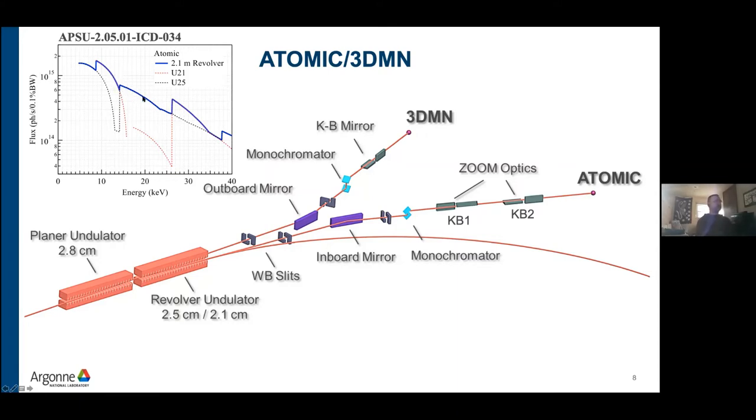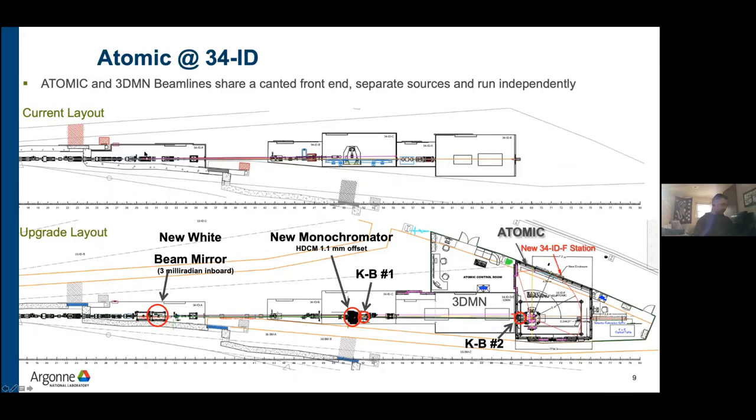The undulators we chose were a 2.5 cm period and a 2.1 cm period, giving a composite tuning curve across the entire bandwidth of the beamline. We'll probably spend most of our time between about 10 and 15 keV, though we might end up spending more time at much higher energy. We'll have a white beam mirror to give separation between the beamlines, and a monochromator which is removable to allow pink beam experiments. We've been doing a ton of work on the development of the zoom optical system.